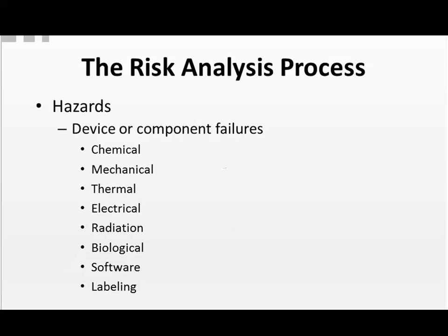Now, some potential hazards that may need to be evaluated include such things as toxicity, flammability, and reactivity of raw materials and waste, sensitivity to environmental factors such as temperature and humidity, mechanical or electronic hazards, and human factors associated with the operator-device interface. The patient-device interface can also be hazardous because of unsafe or ineffective delivery of energy, administration of drugs, or control of life-sustaining functions.